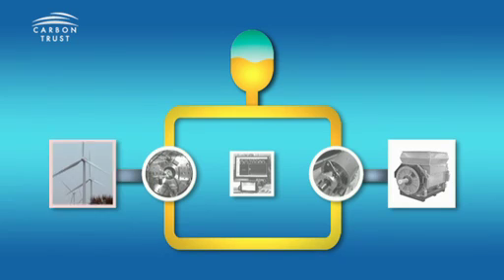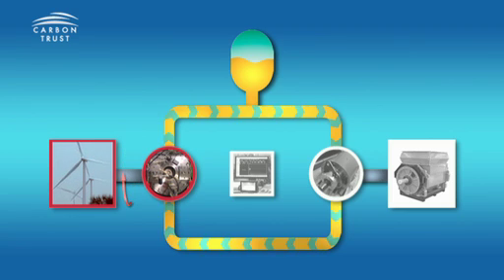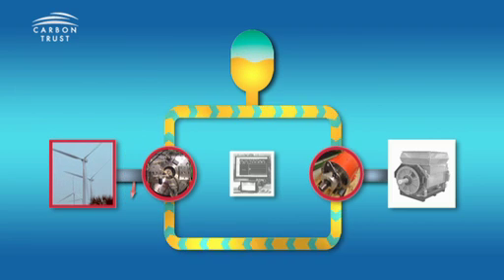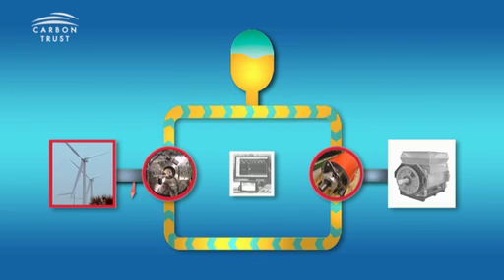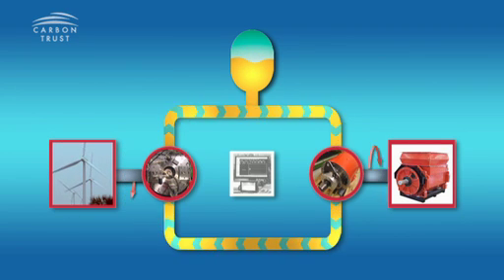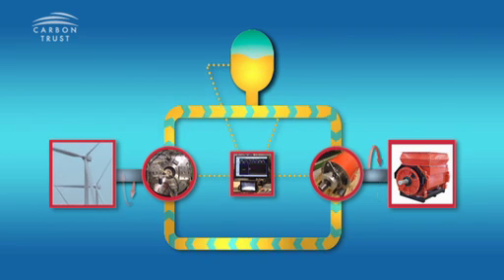The wind drives the propeller, producing torque at its shaft. This drives a pump instead of a gearbox, producing fluid power — pressure and flow in a hydraulic circuit — which in turn drives a hydraulic motor whose displacement is smaller than the pump, so it is able to drive the generator at a constant high speed. The whole system is continuously controlled and monitored by a computer.